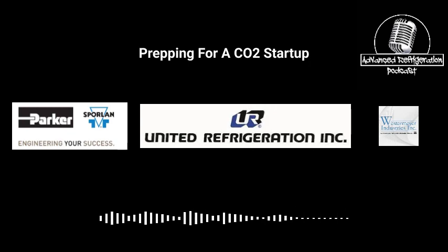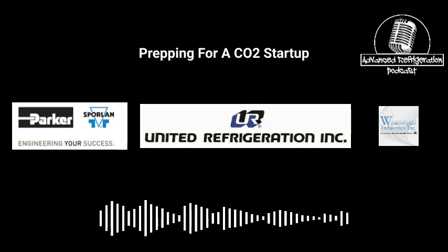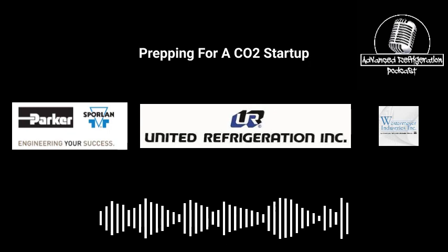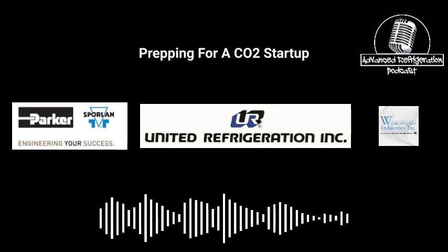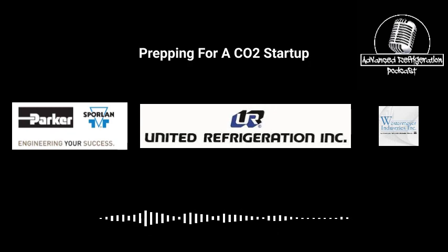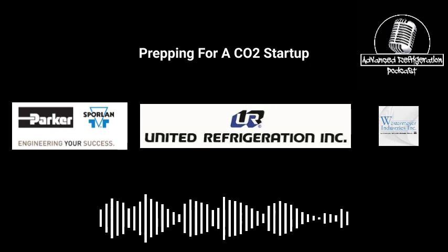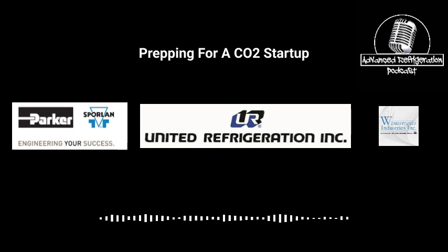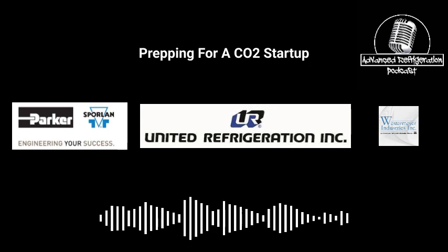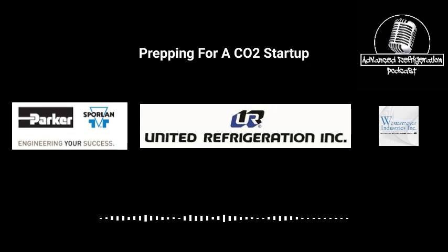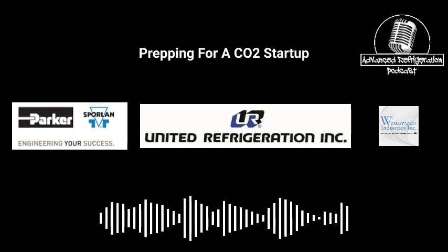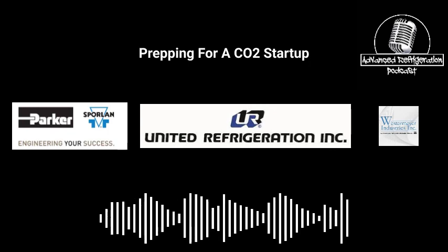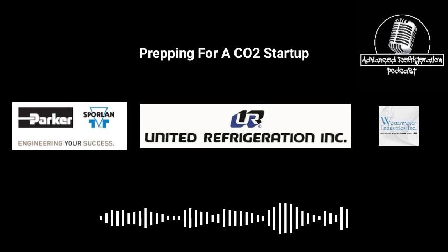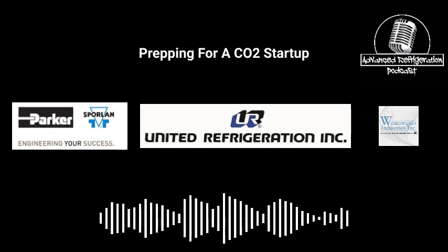Yeah. Well, typically for most transcritical startups, from my understanding, for any store, whether it be Target, Walmart, whatever, you usually pressurize that part of the system to about 100 pounds less than what the actual physical relief is set for. Is that what you're seeing out there? There is no spec for either one of those customers, including Aldi. Really? They leave it up to the manufacturer, which most of the time aren't pushing it. So I generally try to bring it up to like 1,500-1,600 pounds on the high side. I mean, without the blank off plates, you're kind of screwed anyway, because it's going to bleed backwards to a compressor. You're going to get a little bit of bleed down. All I care about is if it explodes or not.